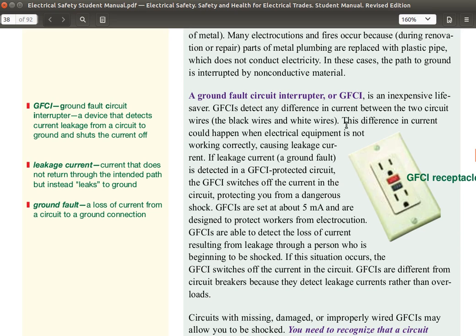GFCIs detect any difference in current between the two circuit wires, the black, that is live, and the white, neutral in America. In other countries, you may have red wire for the live and blue for the neutral. This difference in current could happen when electrical equipment is not working correctly, causing leakage current. If leakage current, that is a ground fault, is detected in a GFCI protected circuit, the GFCI switches off the current in the circuit, protecting you from a dangerous shock.